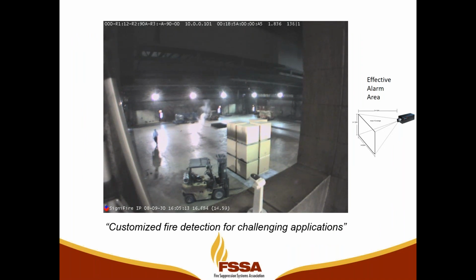The video that you're seeing now is the UL test facility. The engineer lit a 4-minute calibrated smoke emitter. Video analytics analyzes the entire field of view of the screen of the image. All the pixels are being analyzed with all the algorithms that are enabled. The field of view of a video analytics camera is shaped similar to a pyramid. So it's about 82 degrees field of view horizontal, 64 degrees field of view vertical. As you can see, the image is floor to ceiling here.